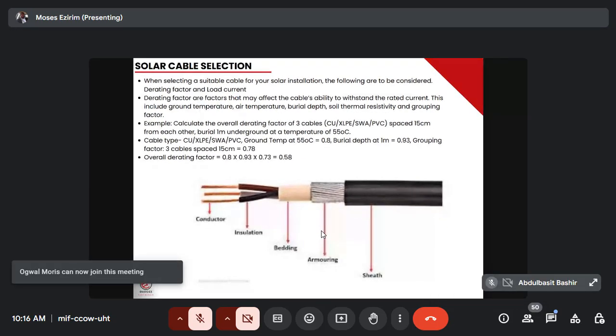I've seen cable catalogs where they'll tell you the rating in air or in ground - I'm sure you must have seen that before. Because inside the ground is different from being suspended in air. There are a lot of factors involved - this is what the derating factor is all about. Derating factors are factors that may affect the cable's ability to withstand rated currents. This includes ground temperature and air temperature.